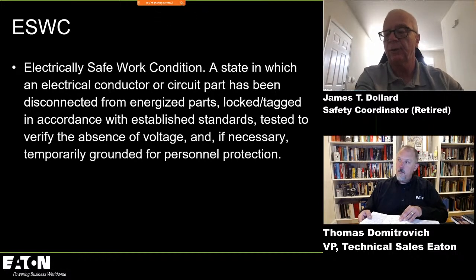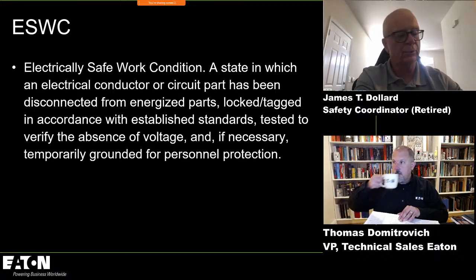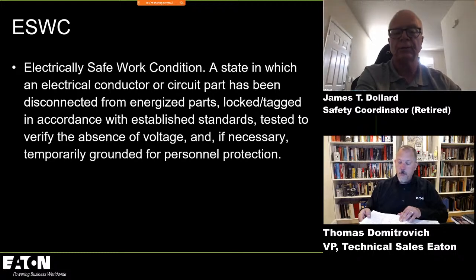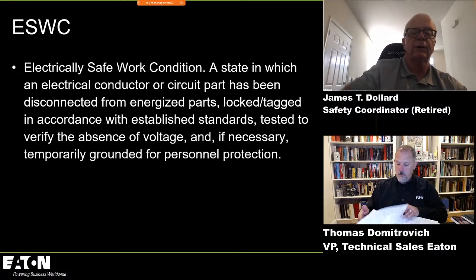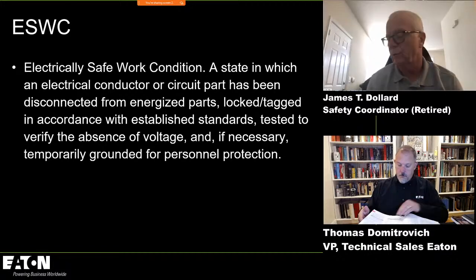Now, 1910.333(b)(2) requires those written procedures to be prescriptive, and then they should be tied to the steps to verify an electrically safe work condition in NFPA 70E 120.5. Then we test to verify the absence of voltage. 70E says you have to test your test instrument first, verify, test your test instrument again. And if necessary, then we temporarily ground for personnel protection.